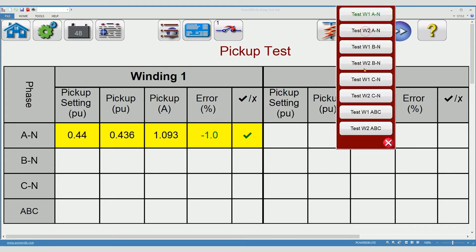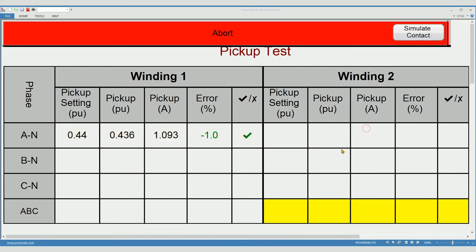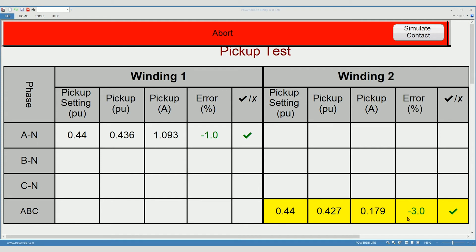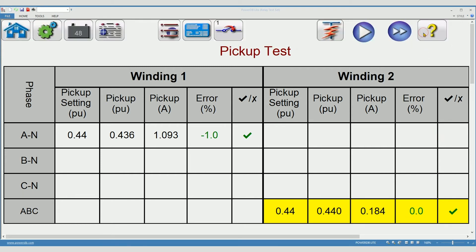Now I'm going to move to the last test on the list to save time. Once again, you notice the nominal values are shown. Pickup values are changing. As soon as it turns green, it's a passing test. I will click simulate button. Clearly you would normally execute all tests, but to save time, this is good enough.